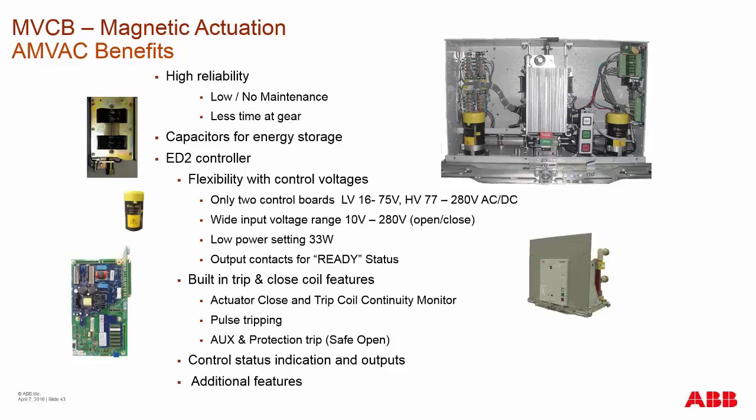Capacitors are your stored energy for this type of breaker — they act like a charging spring in a standard spring charge breaker. Then you have the ED2 control board. We have two control boards: one low voltage board and one high voltage board, with the input control voltage providing the charging power and operational power for the breaker. The high voltage board operates from 77 up to 280 volts AC or DC, but will actually charge with only 40 volts going in — it just takes longer.